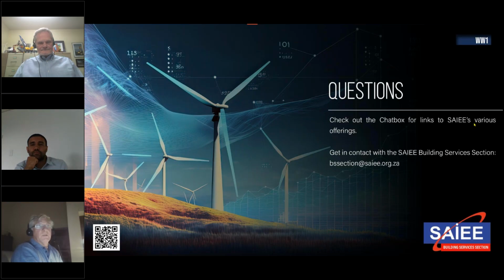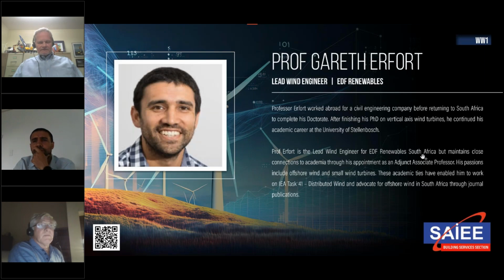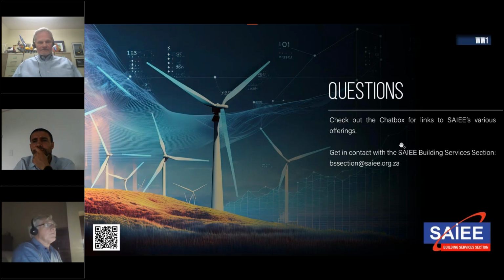Here's an interesting one: what maintenance would the blades require over the life of the turbine? That depends on a couple of things: the tip speed they operate at, how much dust or bugs are in the air, and the coatings used to protect against abrasion. It can be an issue, but in the small wind industry there's a lot of experience with long-lived blade life, and I think the main tier 1 suppliers know how to protect the blades for extensive periods.